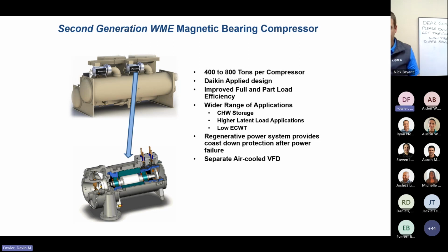We have what we call inverted operation. We can take entering condenser water temps 5 degrees colder than our leaving evaporator water temps without the need for additional head pressure control. We can start up and operate there for as long as we can get that colder condenser water available. Gives us very good performance and a lot of times can eliminate the need for having a water side economizer on site to take advantage of those colder months.